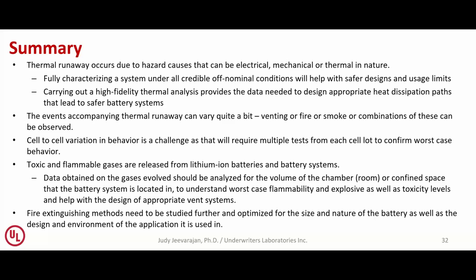Toxic and flammable gases are released from lithium-ion batteries and battery systems. The data on gases evolved from your battery type should be analyzed relative to the volume of the chamber or confined space where the battery is located, since that's where the gases will be released. This lets you understand your flammability and explosive limits, as well as toxicity levels, and helps you design the vent system appropriately.